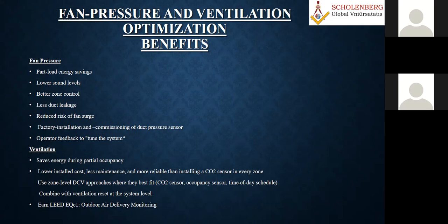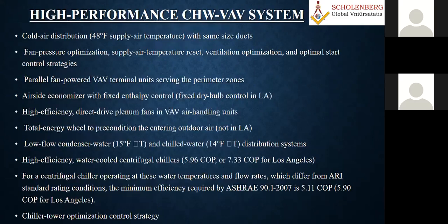And then your fan performance curves, you have to study very carefully, because majority of the time, our AHUs normally work on part load condition. So this we normally do at the simulation level. So fan pressure and ventilation optimization benefit, for that also we have a point, just highlighting that. So now coming to the high performance chilled water system, variable system, which I will be talking about now.